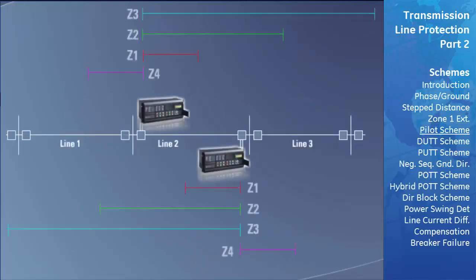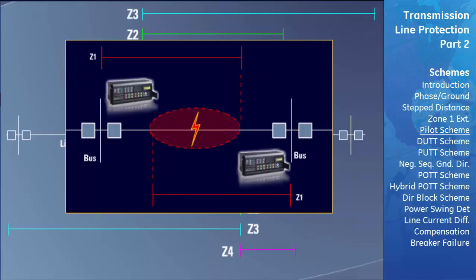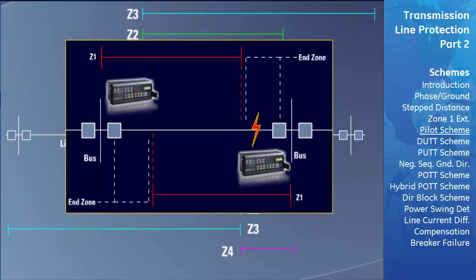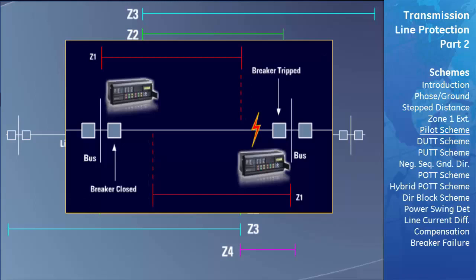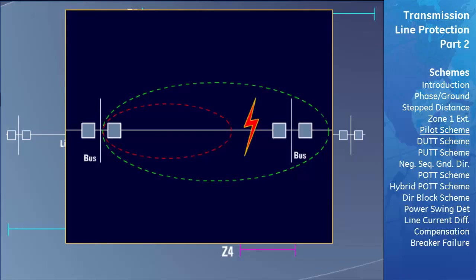All pilot-aided distance protection schemes are based on the basic concept of stepped distance protection. On a stepped distance scheme, a fault in the midpoint of the transmission line within both relays' Zone 1 will be cleared instantly. However, if the fault is in one of the end zones, also known as a close-in fault, it will not be cleared instantly at both ends. The fault is cleared instantly by Zone 1 of the relay near the fault, but the relay at the far end will not clear it until Zone 2's time delay—typically 250 to 400 milliseconds—has expired. The main reason to use pilot-aided schemes is to speed up the clearing of faults in this end zone.